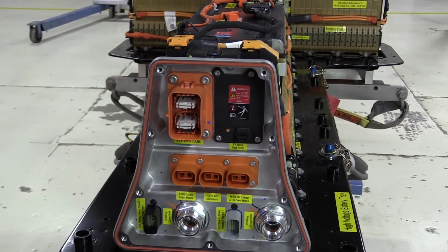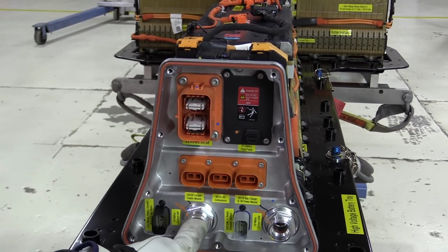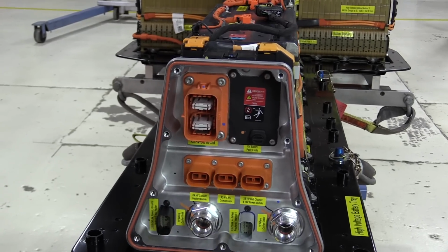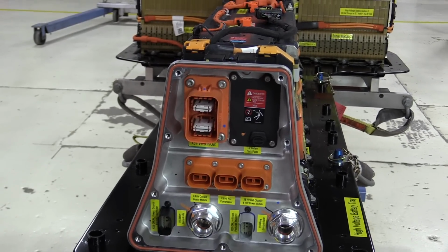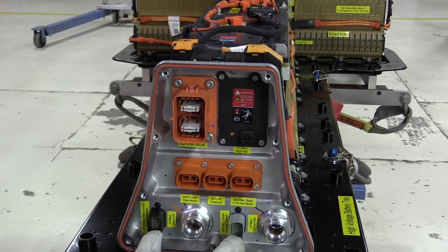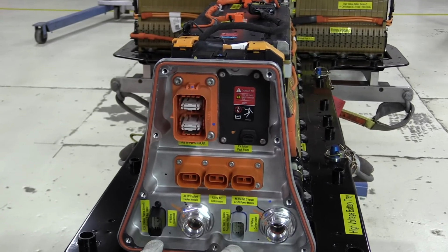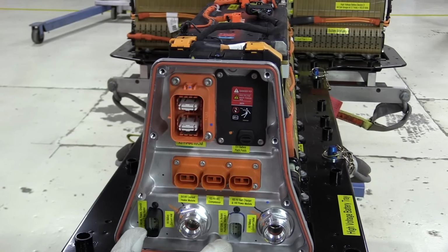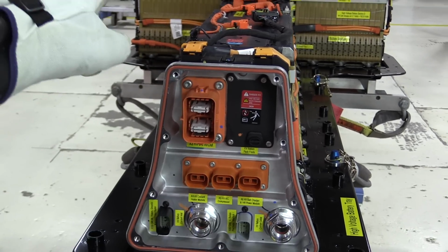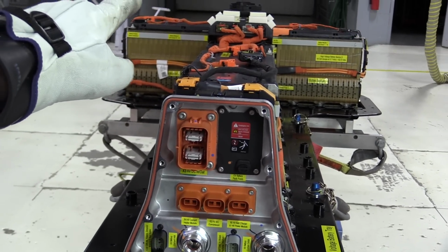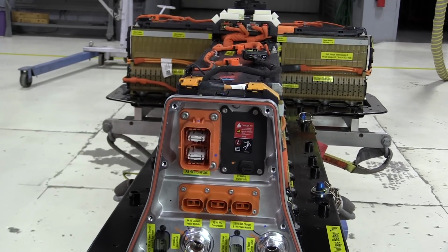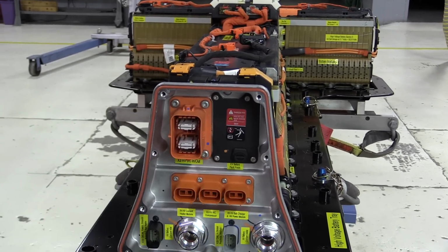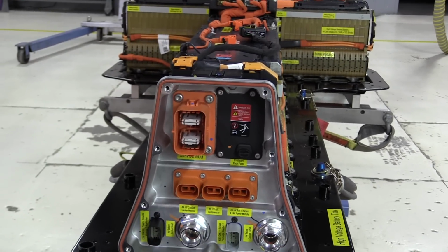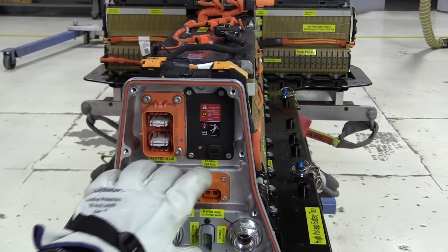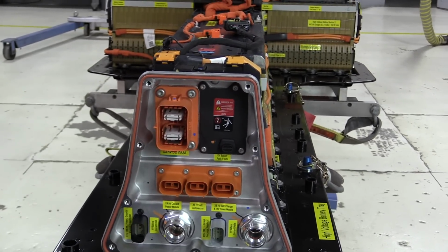We have a coolant inlet and a coolant outlet for this liquid-cooled battery, and then we have low voltage connections right here for the control of the contactors, relays, heaters, and everything else, as well as communication with the battery energy control module, the computer inside of the battery. Under this cover right here, we have high voltage fuses to protect all three of these circuits right here.